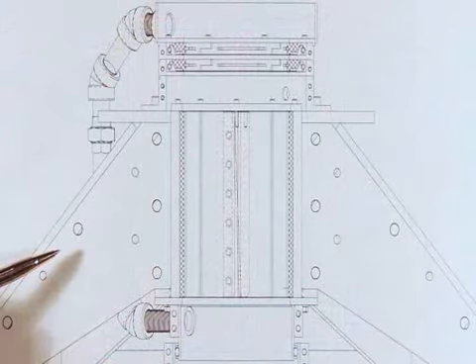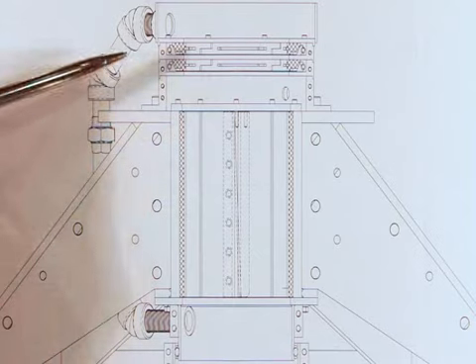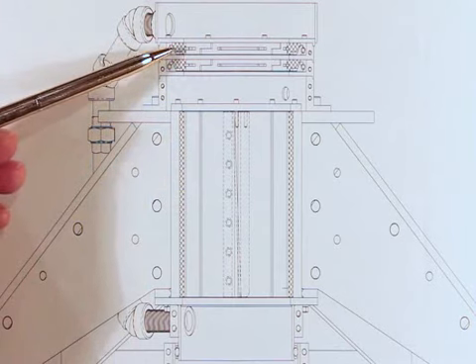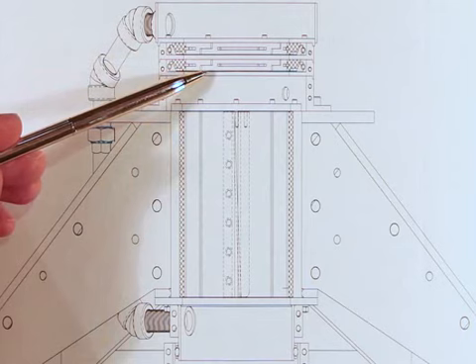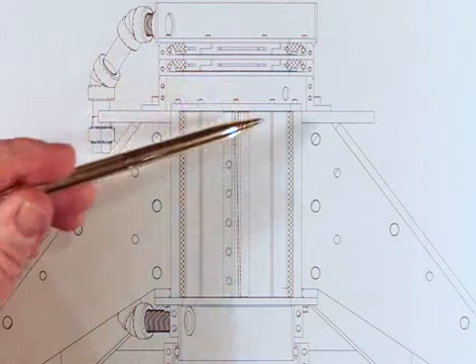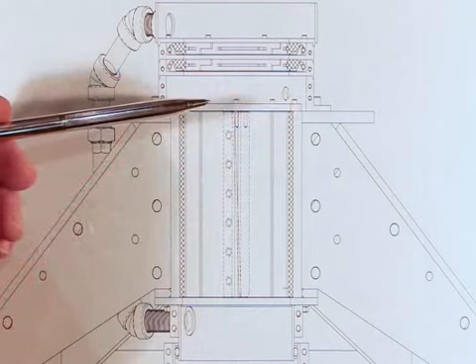The water-lubricated conversion design uses filtered water to lubricate both bearing and seal. In this view, we see a 2-row segmented polymer seal positioned above the bearing. Below the seal are 2 ports for injection of the pressurized filtered water. This water flows down through the bearing and also up through the seal.